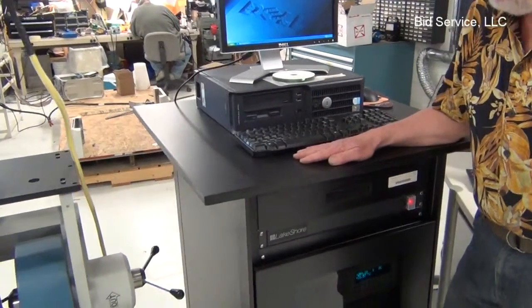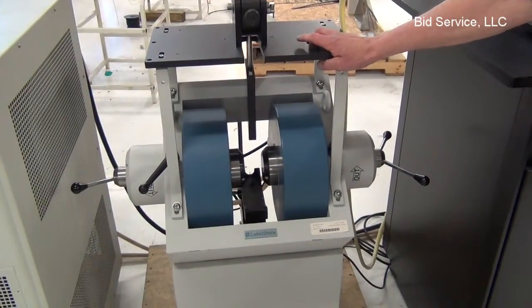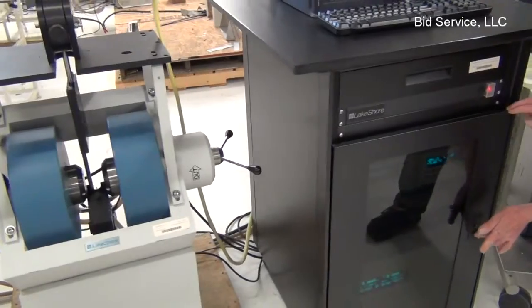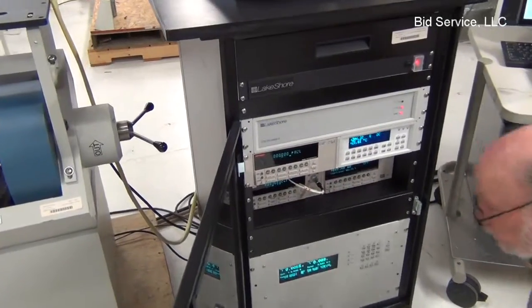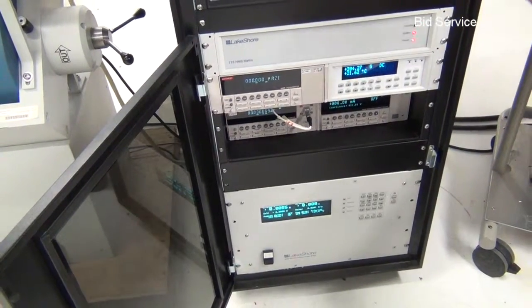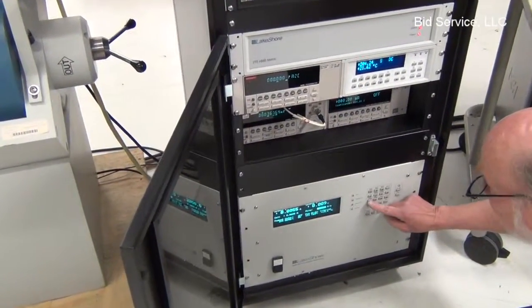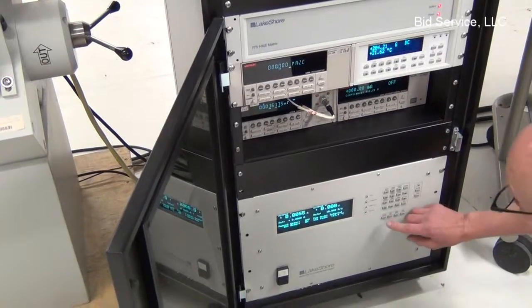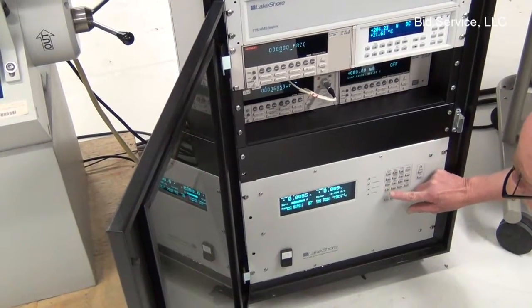The two units work in unison, and part of the equipment is the specially designed electromagnets that are precisely controlled by the bipolar magnet power supply. To illustrate how the magnet works, we can turn power on to the magnets immediately, or we can slowly ramp it up and slowly ramp it down. For purposes of this demonstration, let's say I put in a ramp rate of 10 amps per second and a current value of 20 amps.